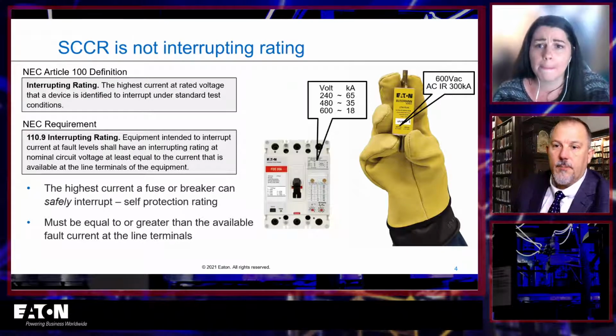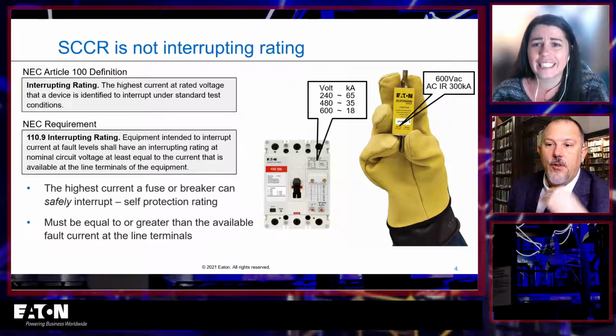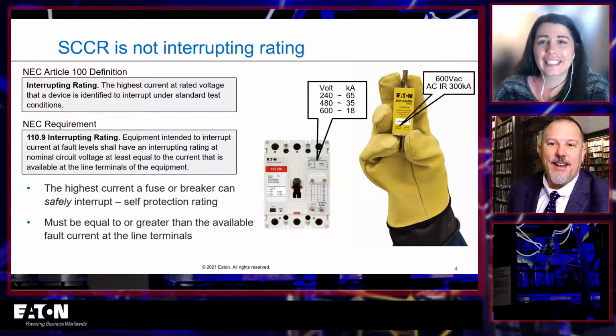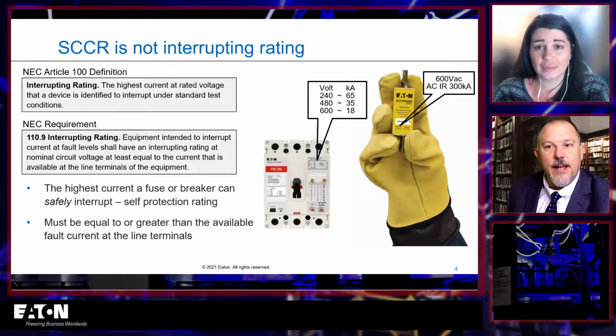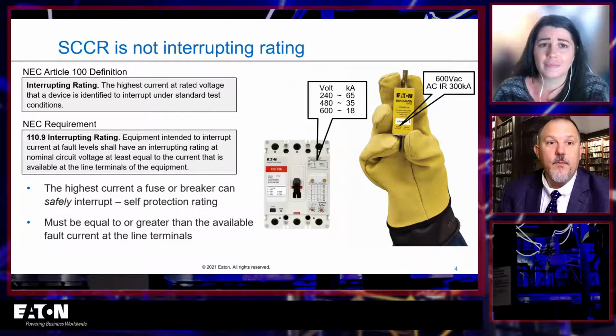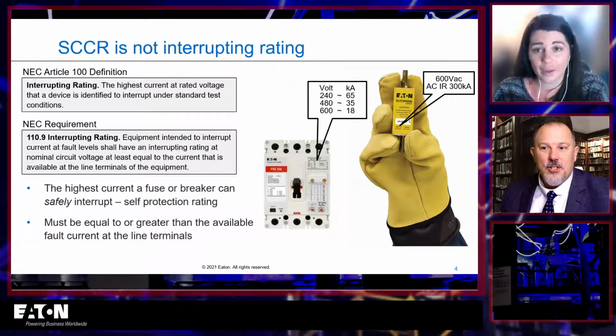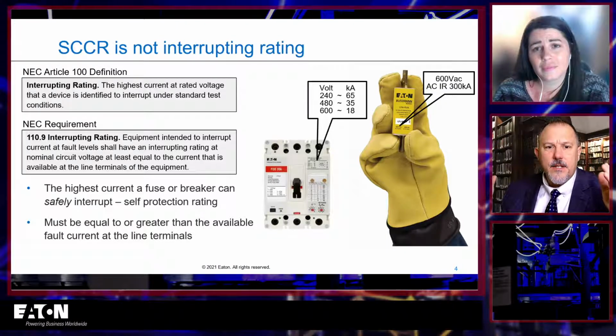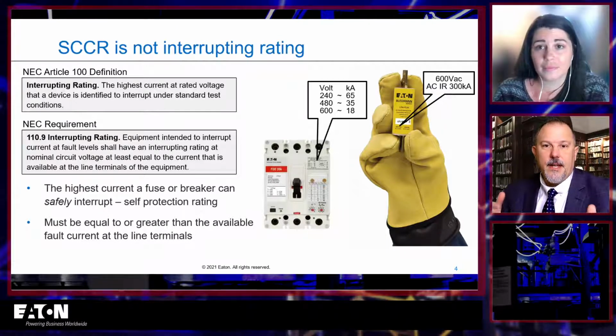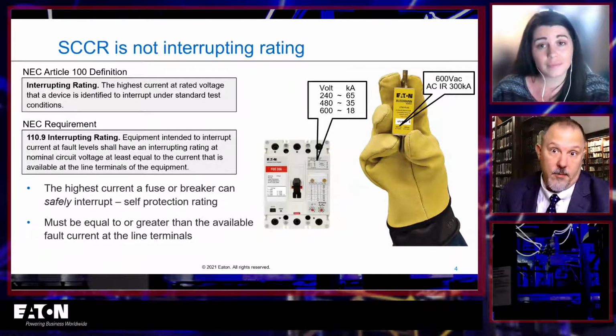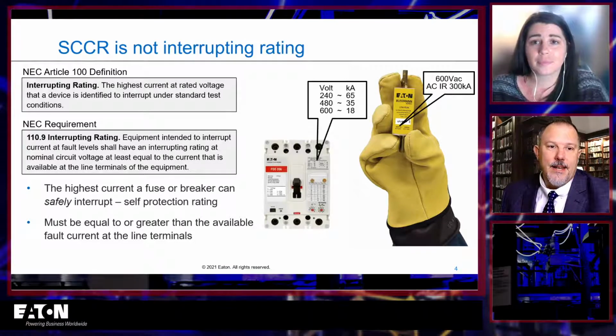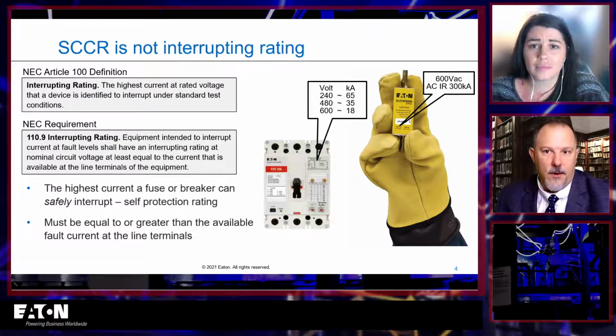Now, David Rodriguez brings up a good point. It's a pet peeve of mine. I don't like the term AIC rating because AIC is amp interrupting current rating. And to your point, interrupting rating is around the overcurrent device. It's not around everything else that's around it. So it is important to understand that, and when you see something that has an AIC rating, yes, the short circuit current rating may be based upon the highest interrupting rating device or the lowest interrupting rating device that's in that piece of equipment, but it's not an AIC rating, it's an SCCR rating.